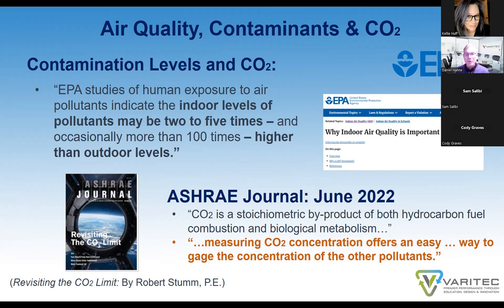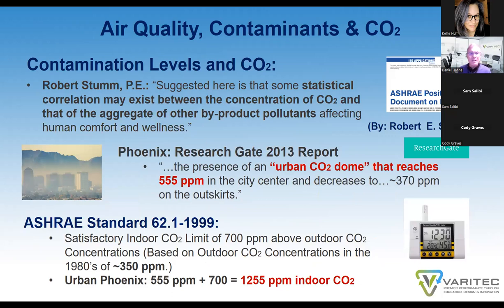And this is per a very interesting article that was published in June of 2022 by the ASHRAE Journal, written by Robert Stumm. The article of Mr. Stumm goes on to suggest that there is some statistical correlation that may exist between the concentration of CO2 and the aggregate of other byproduct pollutants affecting human comfort and wellness. Well, let's look at Phoenix, Arizona. ResearchGate did a study of outdoor air CO2 concentrations in 2013, and they found that there's an urban CO2 dome that reaches 555 parts per million in the center of Phoenix. In the outlying regions, it decreases to about 370 parts per million at the outskirts.